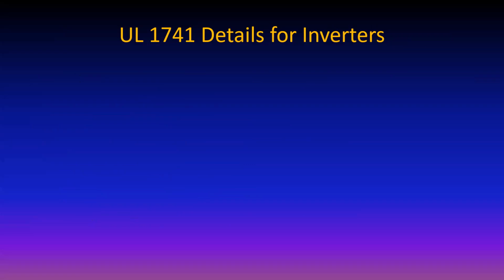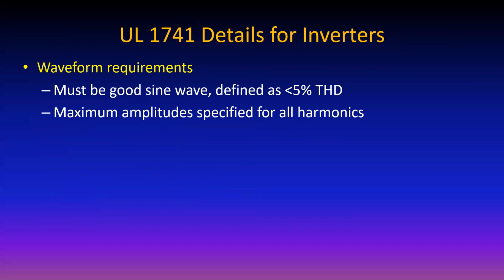UL 1741. Now let's talk in a little more detail on UL 1741. First of all, the requirements on the waveforms. In order to connect to the utility, you have to meet the UL 1741 details. So it has to be a good sine wave, defined as less than 5% total harmonic distortion, and it specifies maximum amplitudes for all harmonics. Right now, every inverter I'm aware of that's on the market is better than utility sine waves, because utility sine waves are generated by rotating machines. And with rotating machines, the design of the machine itself makes it extremely difficult to have a perfect sine wave. You come pretty close. So electronically, you can actually do better than you can mechanically in terms of sine waves.